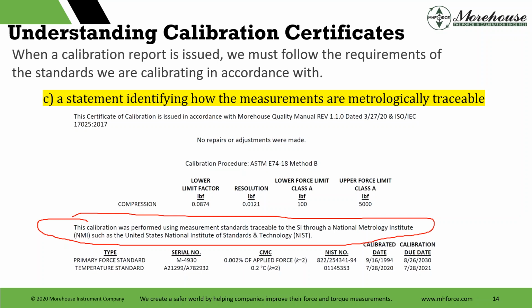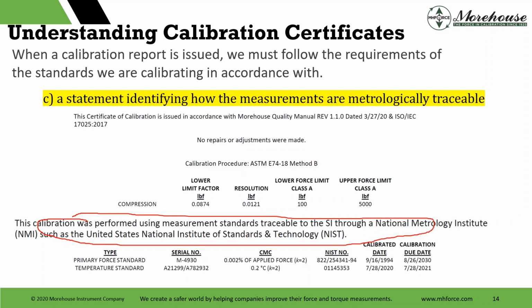So you really need to follow this logic and look at that chain of traceability and see how far it is away and what a lab can reasonably achieve. It's always essential to make sure you're getting the calibration you need, and to look at the lab's measurement capability uncertainty on their scope of accreditation. Per NIST, and this is a quote directly from them, NIST emphasizes that traceability alone does not signify or guarantee fitness for purpose, because this typically requires that the uncertainty associated with the measured value or calibration be sufficiently small to satisfy a particular measurement need. So check your calibration supplier, make sure you are getting what you need.